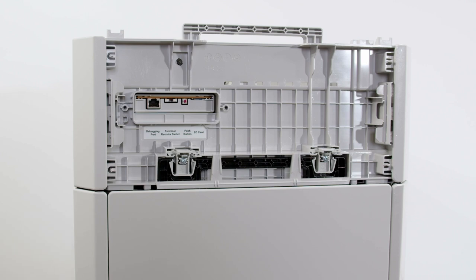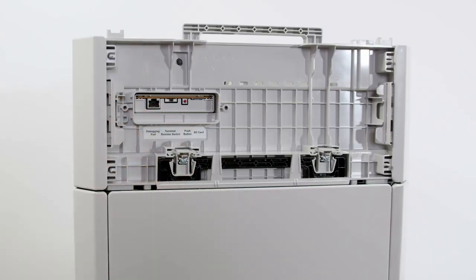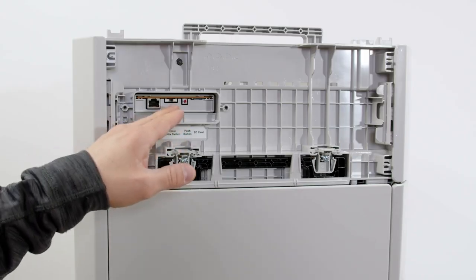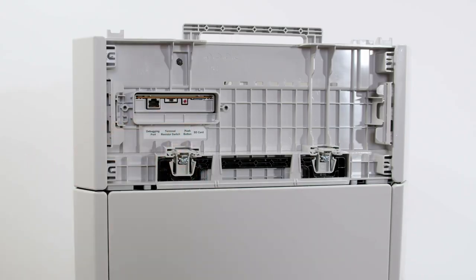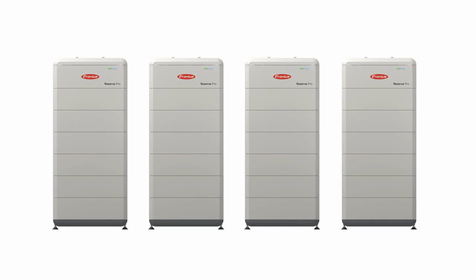Please note, depending on how you install the parallel connection, you need to make sure that always the last part in the communication chain is set to terminal resistor switch on position. Please also note, ex factory, the terminal resistor switch is always set to the on position. Meaning that in our case, we now want to install, for example, 4 batteries in parallel.